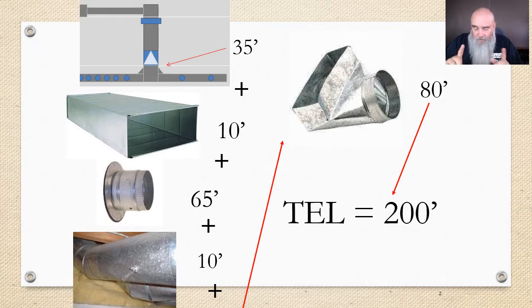So the way this works—and I guess I am going to go through the whole critical path or longest circulation path. This right here is a quick demonstration. When I say this right here, let me turn that pointer on. This fitting right here, when we look in the charts, Manual D will tell us that it's worth 35 feet, 10 feet of actual length.